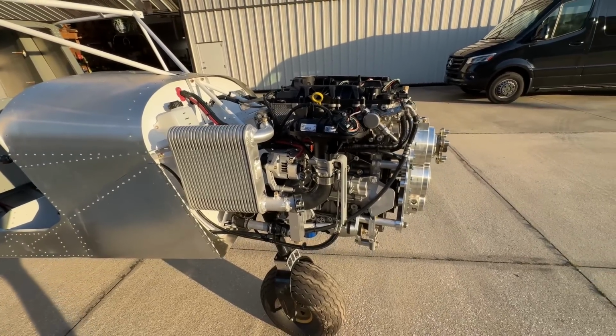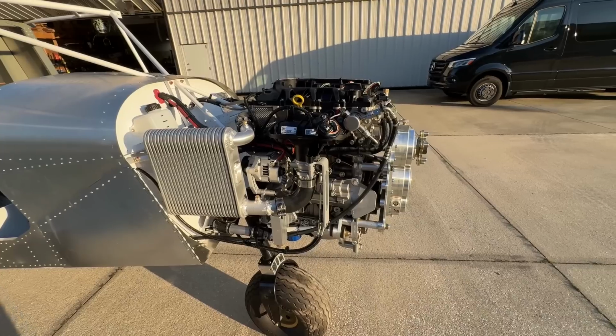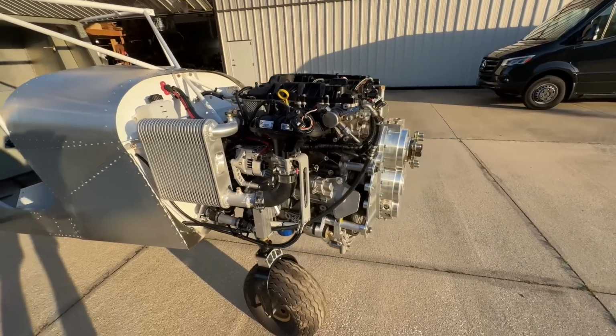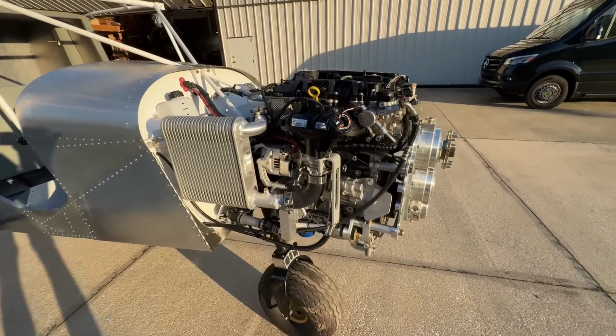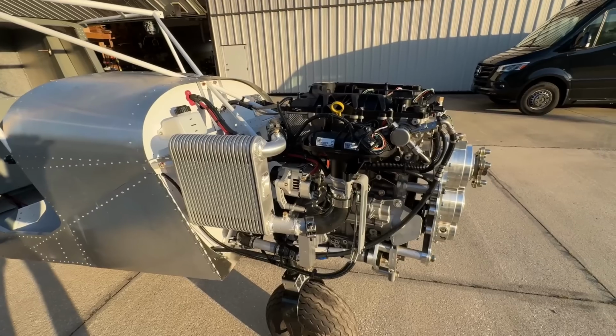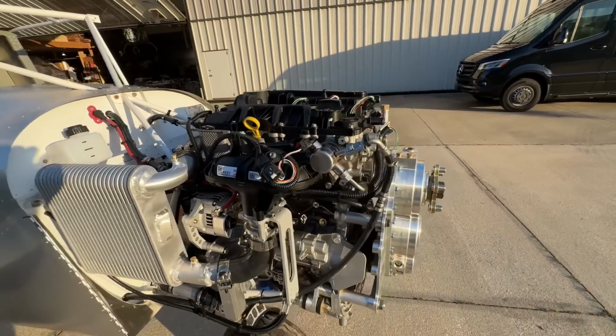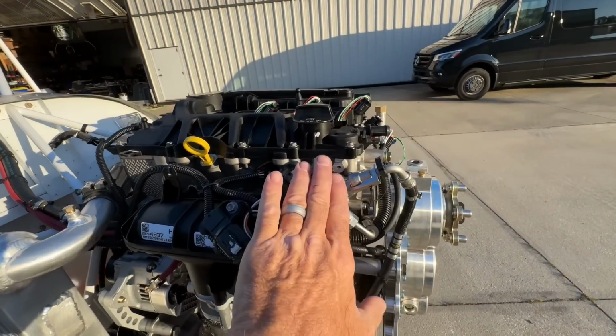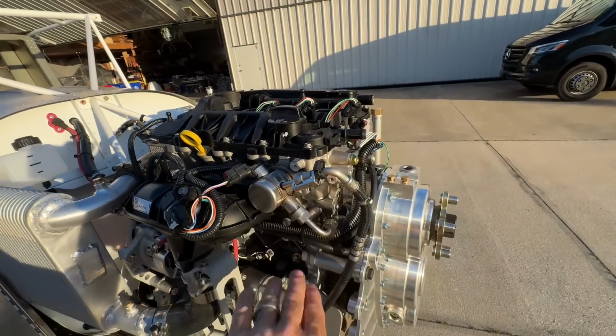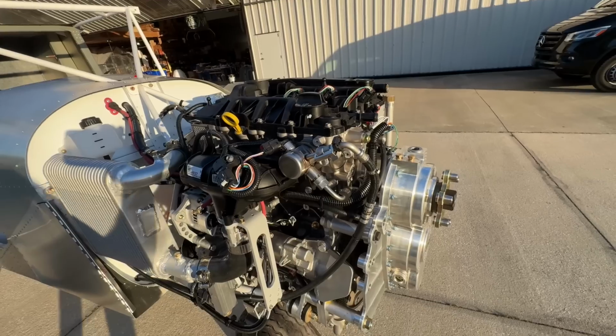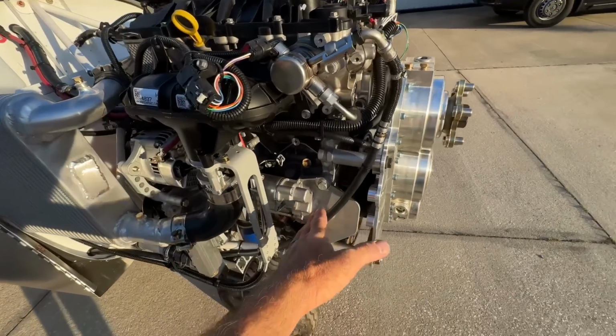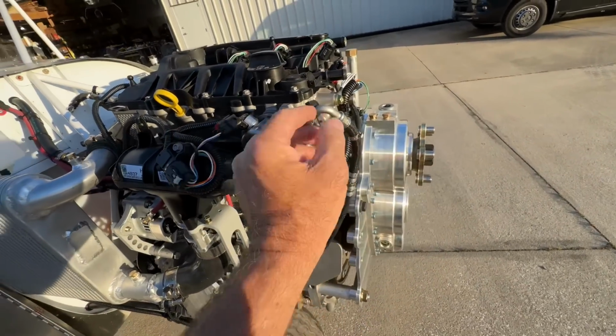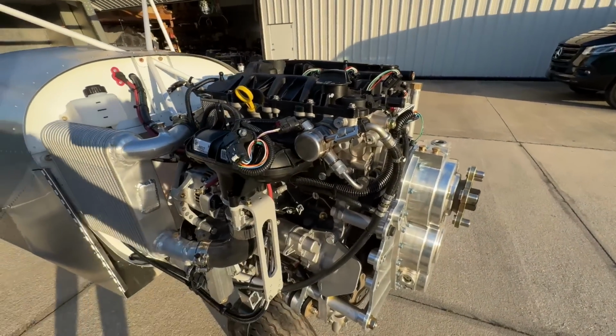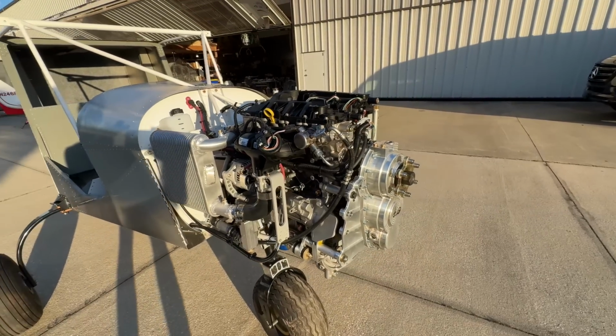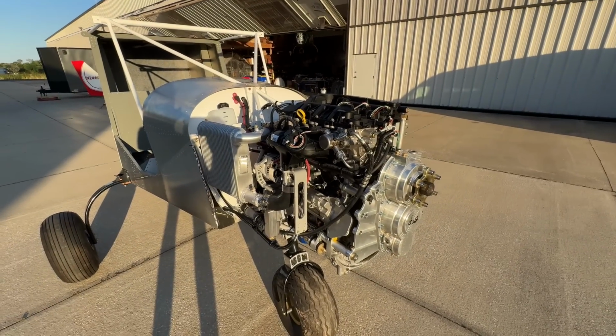Look at our instrument or our store for parameters for this engine. Oil pressure is normal, up to 100, no less than 20. The fuel pressure is high on this engine since it's a direct injected engine, but what you're concerned with is the pressure from the tanks going to the high pressure pump. You want 40 to 50 there all the time. That takes care of the instrumentation of the engine.